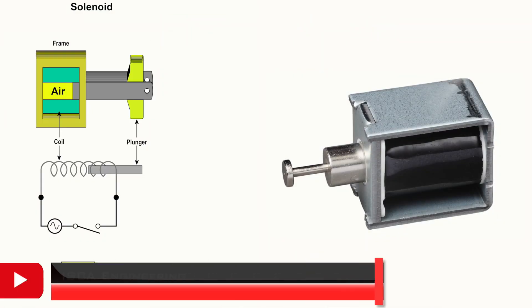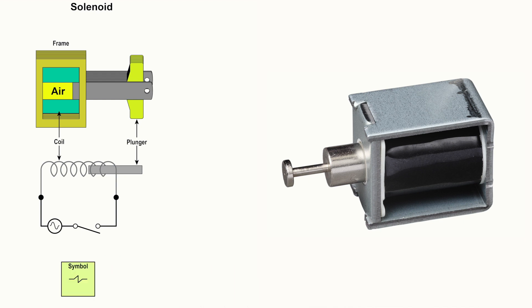A solenoid is a device that is made up of a coil, frame, and plunger. When current is passed through the coil of wire, it exhibits the properties of electromagnetism and a magnetic field is induced within the core and around the coil. When the magnetic field is produced, it attracts the plunger, pulling it into the frame and therefore creating mechanical motion. Solenoids are available in AC and DC, but AC solenoids tend to be stronger in the fully open position due to the inrush current.